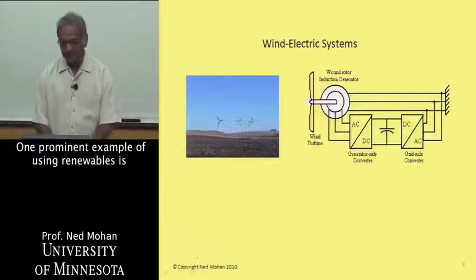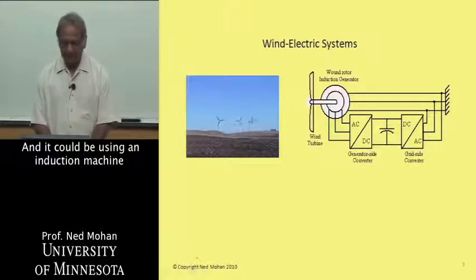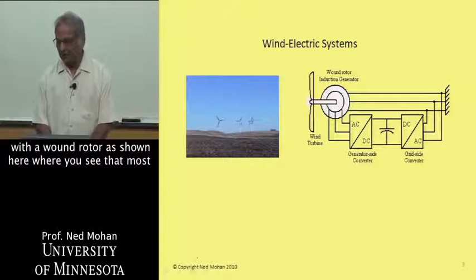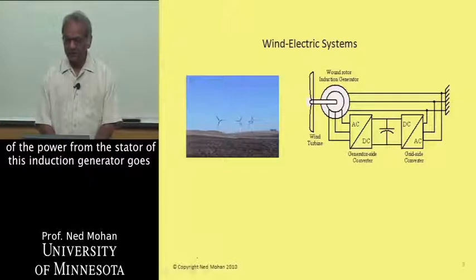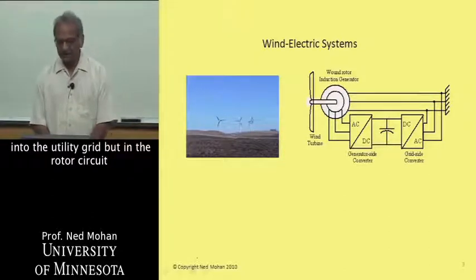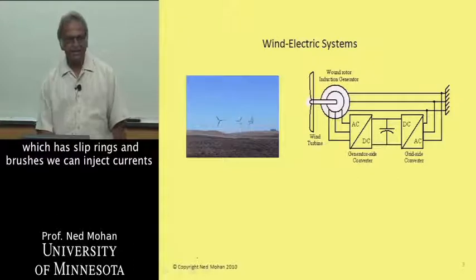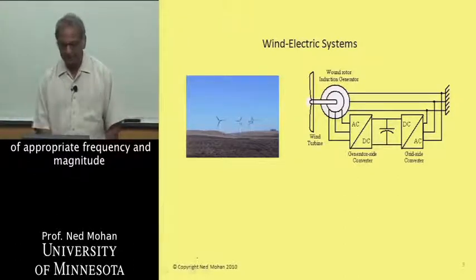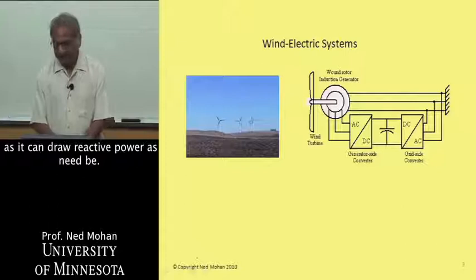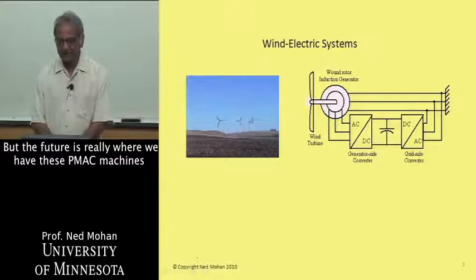One prominent example of using renewables is wind energy. It could use an induction machine with a wound rotor, as shown here, where most of the power from the stator of this induction generator goes into the utility grid. But in the rotor circuit, which has slip rings and brushes, we can inject currents of appropriate frequency and magnitude so that this can provide or draw reactive power as needed.